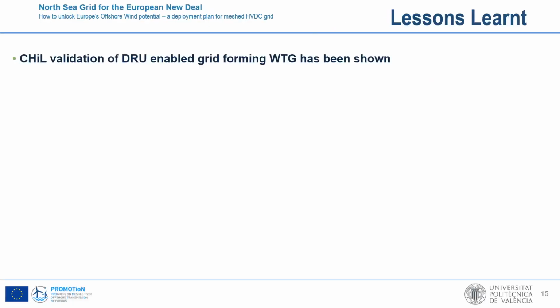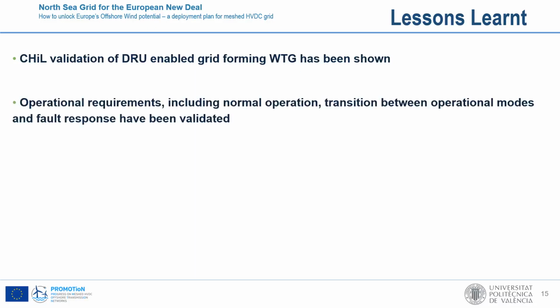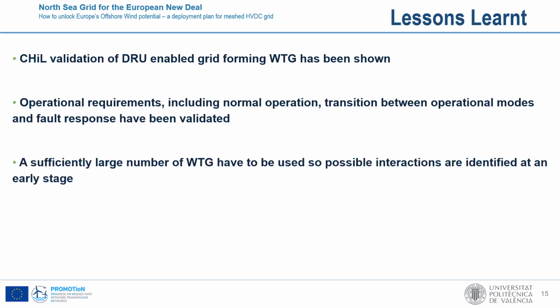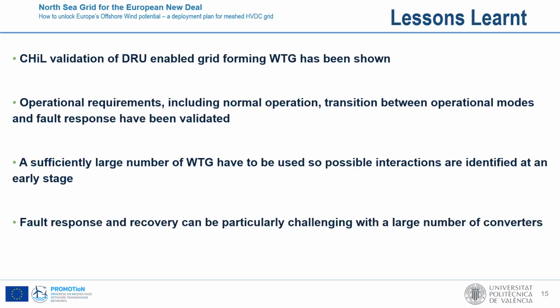we have carried out the control hardware in the loop validation of diode rectifier enabled grid-forming wind turbine controllers. We have considered all the functional requirements for the different modes of operation, both in islanding and in HVAC synchronized, and the transition between the operational modes, and also the fault response to faults in different parts of the system. Something that is very important is to consider a sufficiently large number of wind turbine generators. Otherwise, it is possible to miss interactions between the wind turbines.